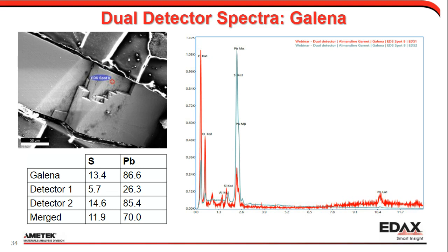The other detector is looking from the bottom up, and that one doesn't have as much additional things going on. There is a bit more fluorescence. We see some increase in carbon oxygen, but we get more reasonable results here. We're relatively close to the known composition of the sample. But if we take the spectra and add them together, things start to go south. You're taking bad data and adding not great, but acceptable data on top of it, and that decreases the quality.